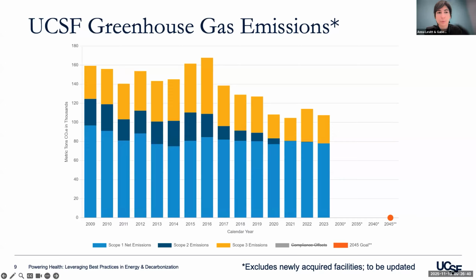Across the board for our hospitals, our decarbonization plan includes maintaining natural gas boilers for heating backup — boilers that would almost never run — as a way to provide heating backup without needing massive diesel generators sized to serve the electric heating loads.